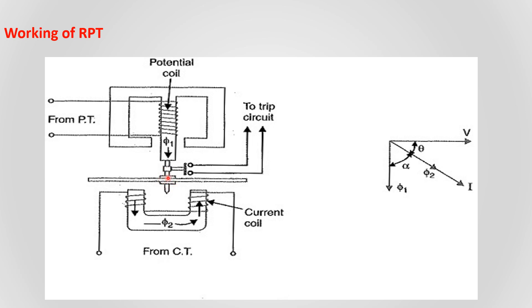Under normal conditions, the disk rotates in the normal direction and the moving contact does not close the fixed contact. But during reverse power flow, the disk rotates in the reverse direction, the moving contact closes the fixed contact, the circuit is closed, and a tripping signal is given to the ACB trip coil, which opens the ACB breaker. In this way we protect the prime mover and generator. This is the working of the reverse power relay.